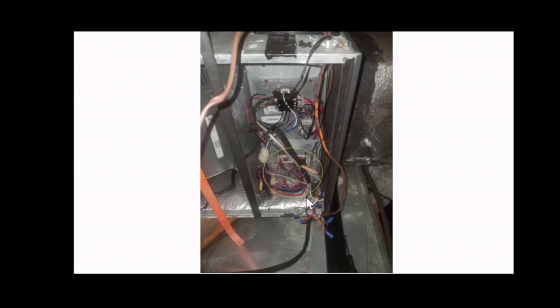another metal area or any kind of area like a clamp or something, it may become chafed, meaning that the jacketing, the insulation, may be broken off, worn off, shaved off through the vibration. So make sure that wires are not touching the metal inside of the frame or the chassis or another wire.